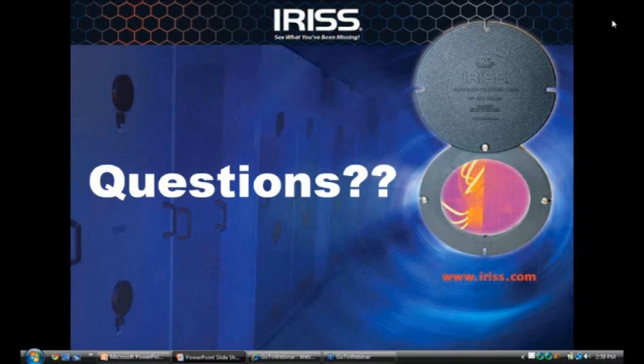I read there's a possibility of incorrect readings through IR windows as compared to an open panel reading. Definitely. It's called transmission rate. The transmission rate of the materials utilized in the infrared windows really depends on many things. You need to know what the transmission rate of the crystal or the polymer or whatever you're using as your lens is. Now, we have what we call a fixed and stable transmission rate, and I'm not going to go into that because it gets very commercial and there's a lot of conjecture, but yes, the transmission rate of the material will change. It can change with age, it can change with temperature.